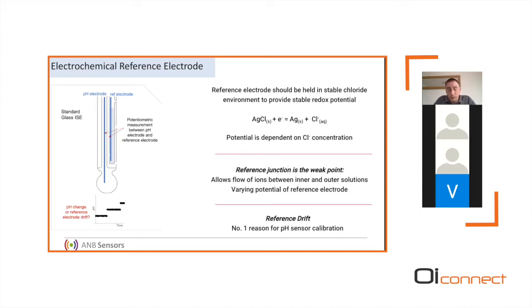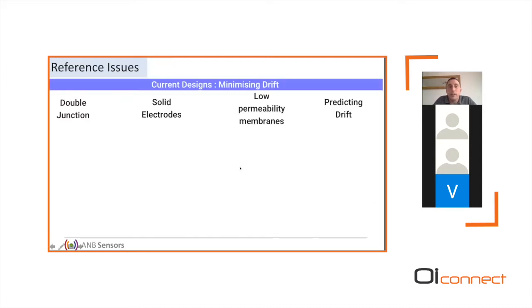And we've spoken to a lot of end users and sensor manufacturers, and they say reference electrode drift is the #1 reason why electrodes need to be recalibrated. If we look at the current designs that are out there, there are ways of trying to minimize that drift using either double junction systems. Solid electrodes have been used. Low permeability membranes have also been explored, and there are ways of predicting that drift. However, in a real life situation, that's very difficult to do.